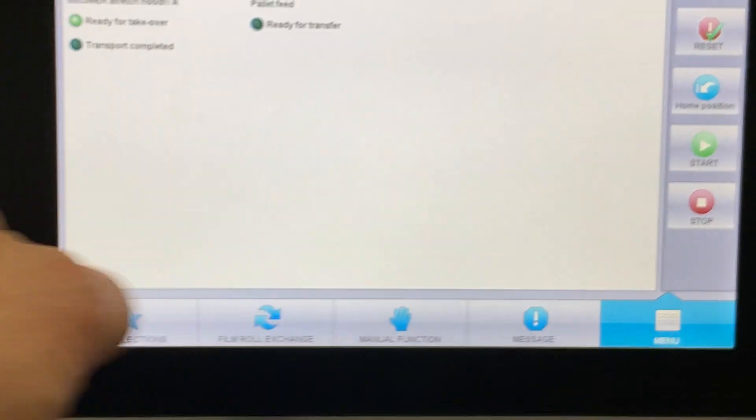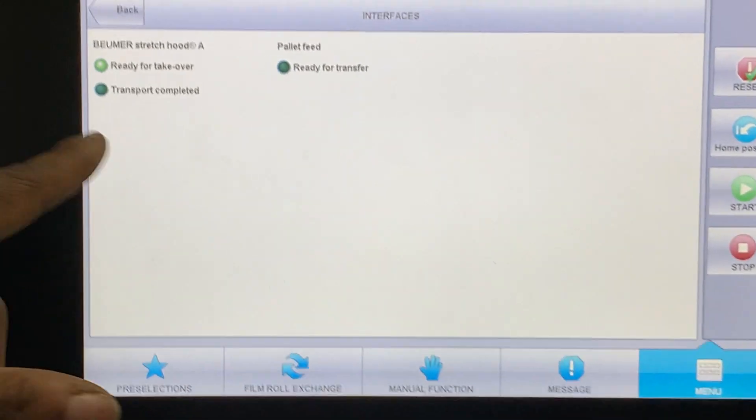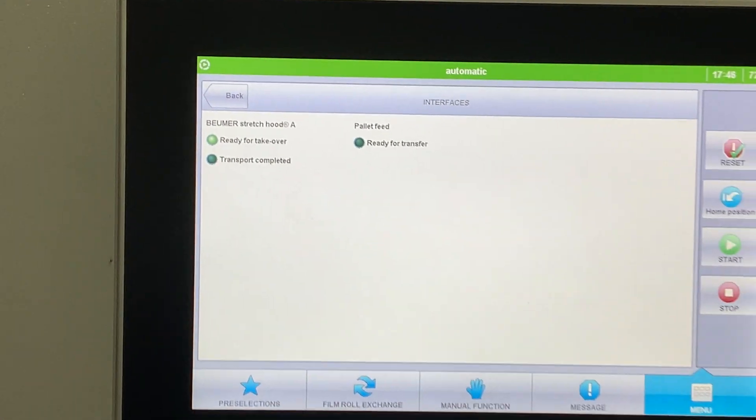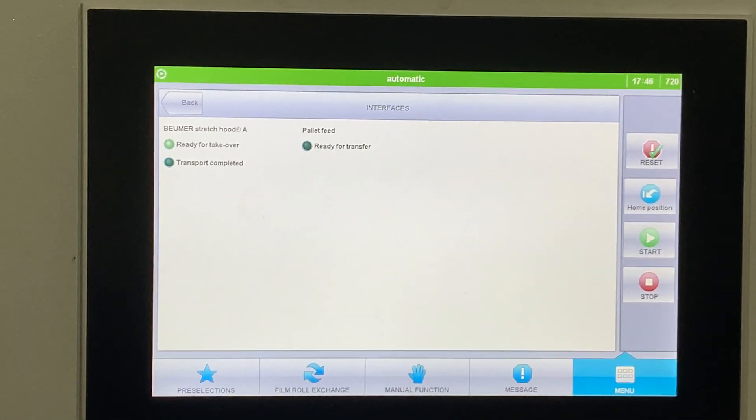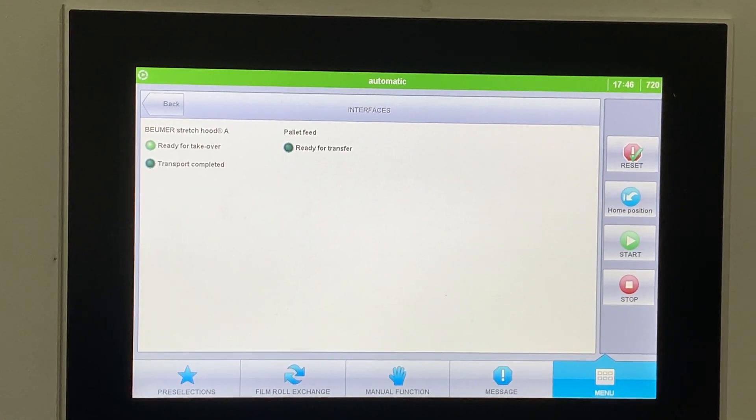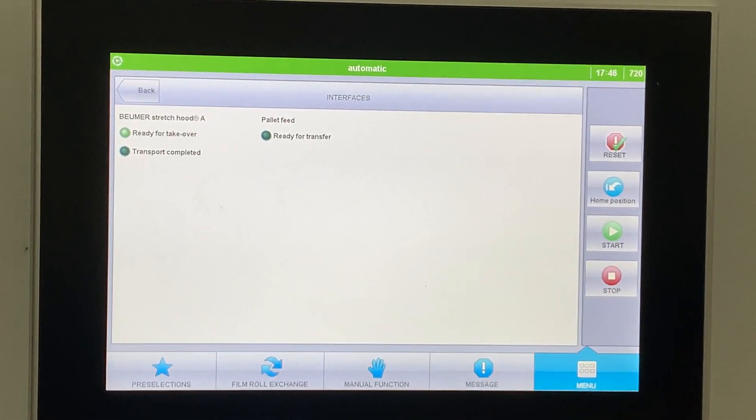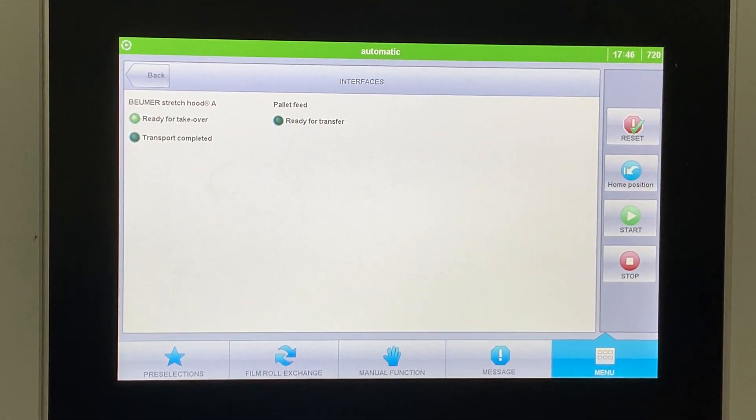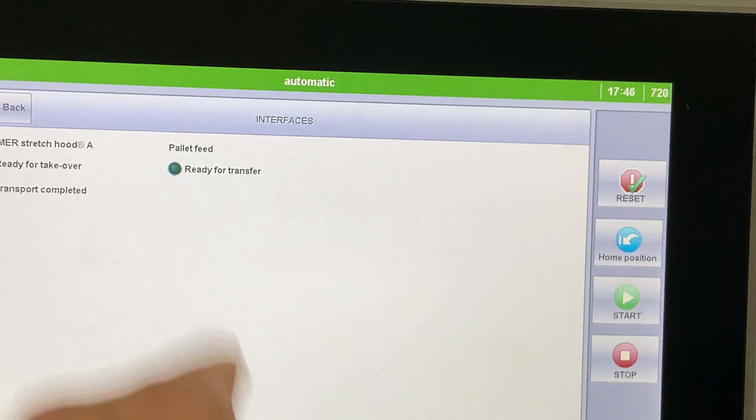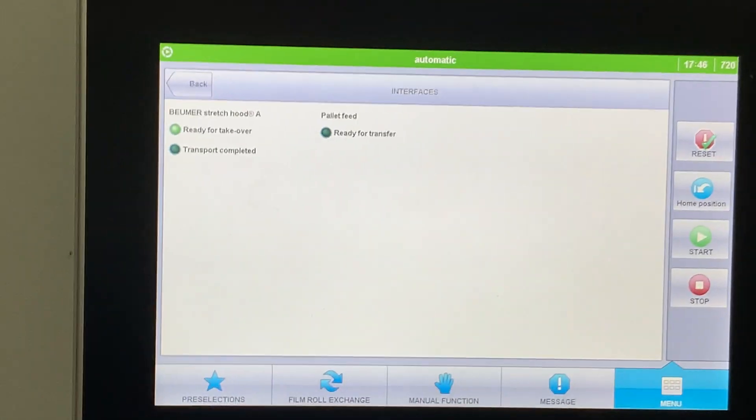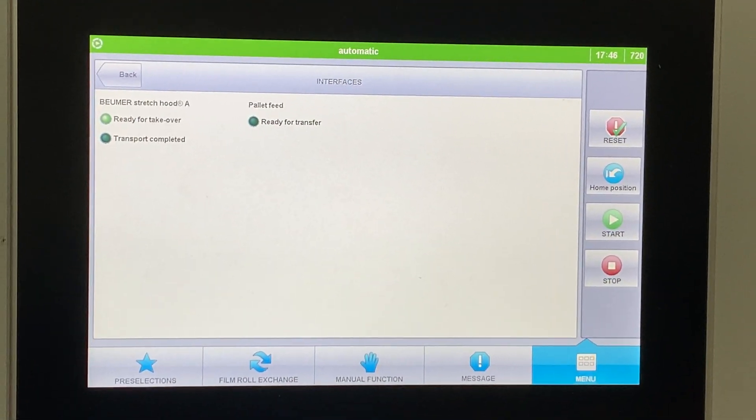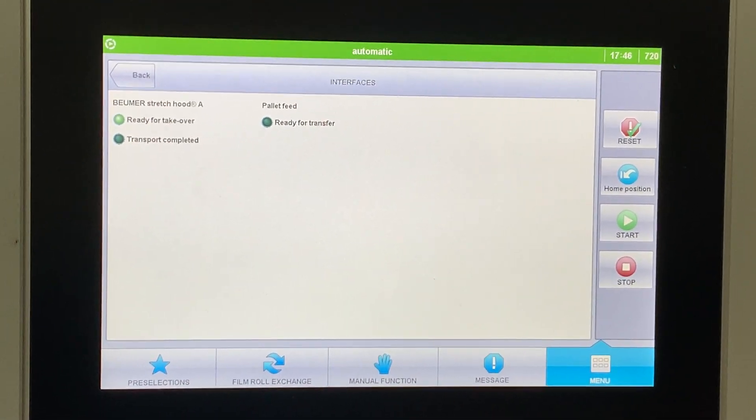This is a way to check if something is going wrong. If they send us something and our motors ain't moving, we can go see you're not sending us a signal but you're sending us a pallet. Something's wrong there. That's more of a maintenance thing when electrical stuff happens. A wire could be loose or something. This is a quick way to check the I/O between the two machines.